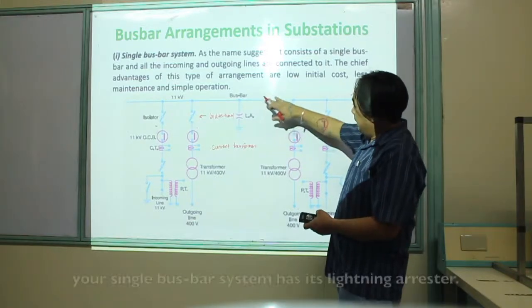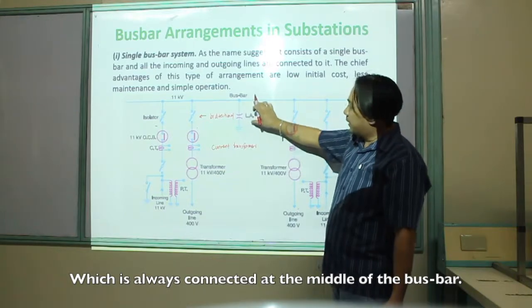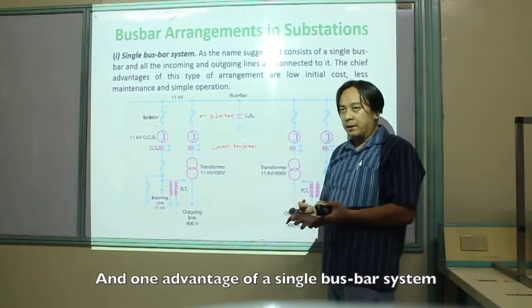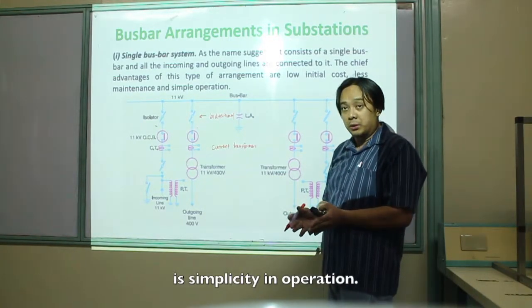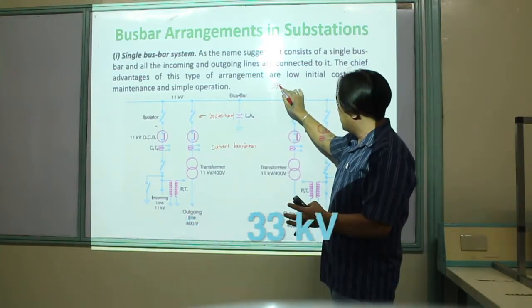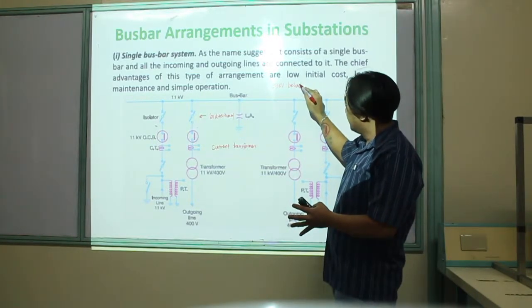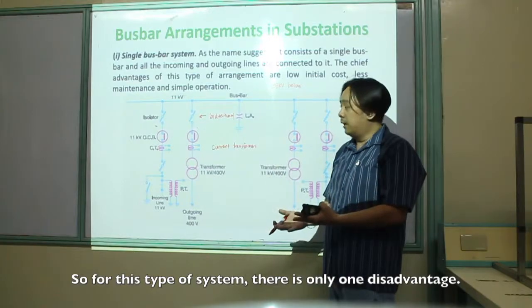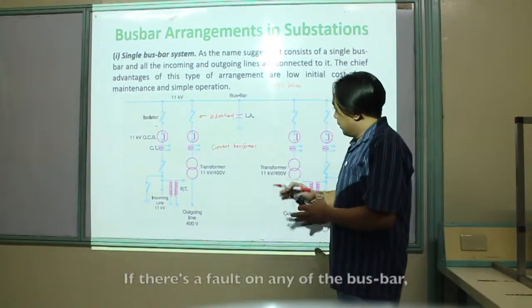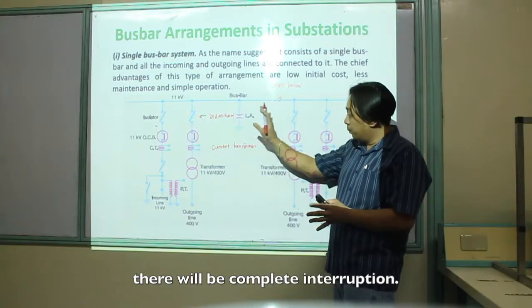Your single bus bar system has a lightning arrester, which is always connected at the middle of the bus bar. One advantage of a single bus bar system is simplicity of operation. Also, this type of bus bar operates at 33 kV and below. However, there is one disadvantage: if there is a fault on any of the bus bars, there will be a complete interruption.